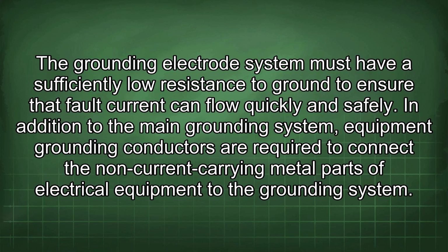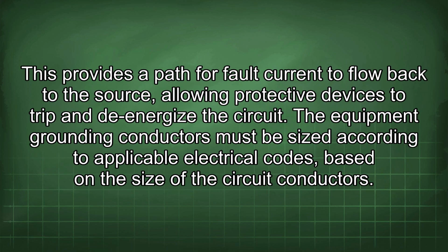In addition to the main grounding system equipment, grounding conductors are required to connect the non-current carrying metal parts of electrical equipment to the grounding system. This provides a path for fault current to flow back to the source, allowing protective devices to trip and de-energize the circuit. The equipment grounding conductors must be sized according to applicable electrical codes based on the size of the circuit conductors.